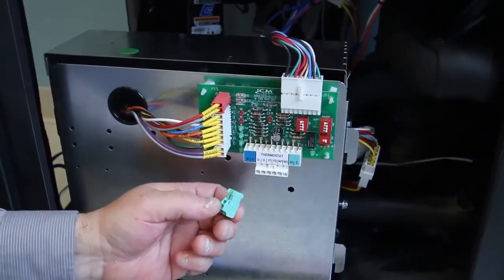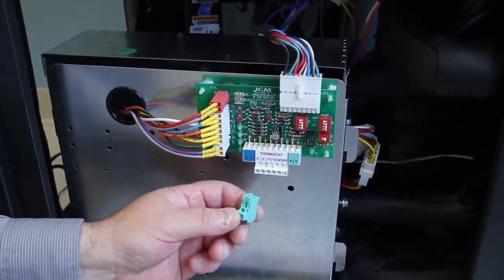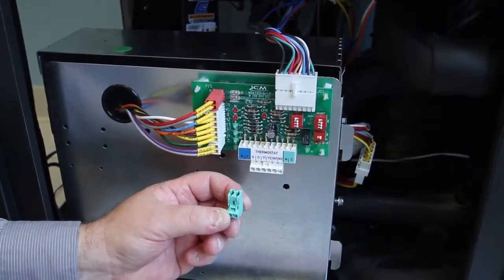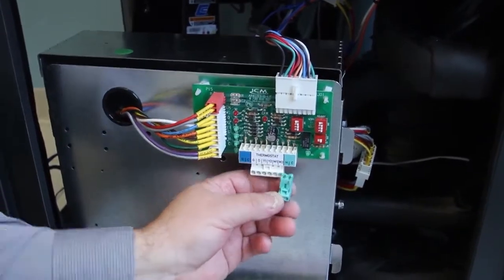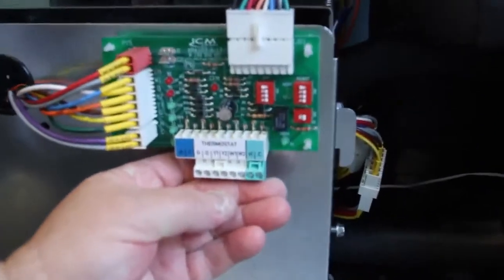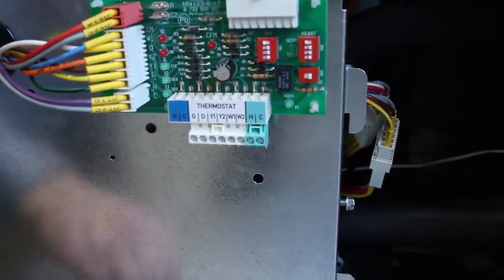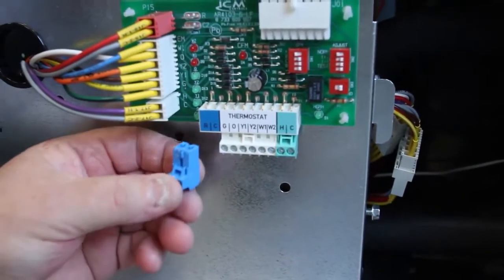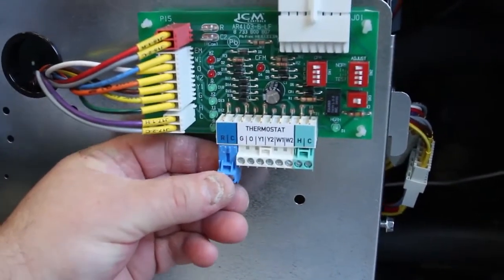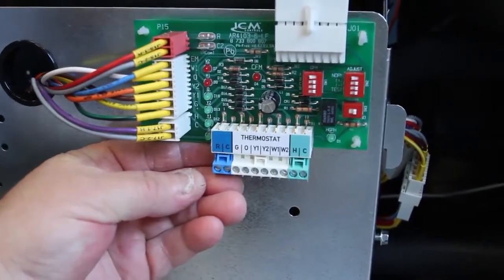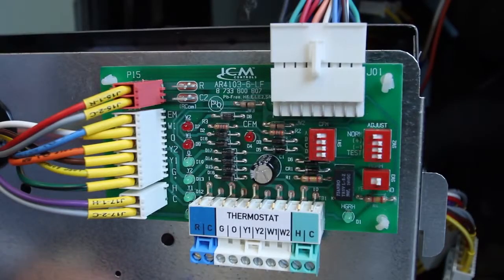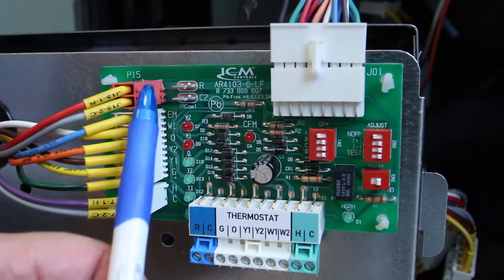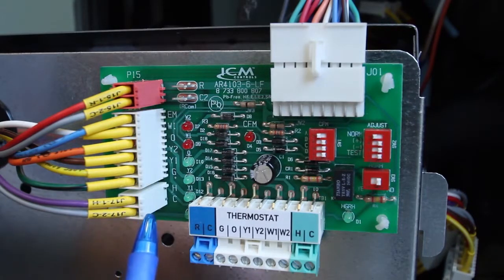The green connector that plugs into the MCI or motor control interface is for dehumidification. We'll talk about that option. And then the blue connector is for your red and your common wires coming from your control. Over to the left of the thermostat block, you will notice several wires connected to the board. These are the outputs to the different components in the system.